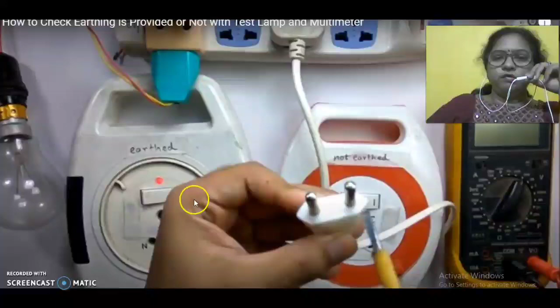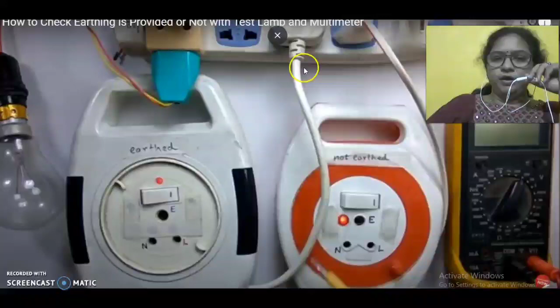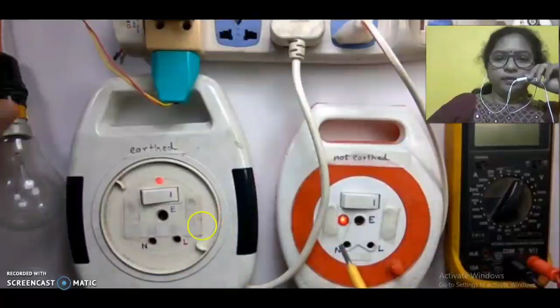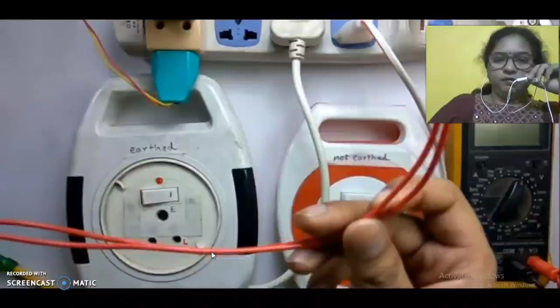Now how to check this earthing? This is a 2 pin socket where neutral and line terminal are there, and earthing is not provided, so this is not earthed, and this is the earthed one. The left side is the supply system which is earthed, where 3 pin is provided. Now whether earthing is there or not, you can check with the help of a test lamp. Here the test lamp means nothing but an incandescent bulb connected with 2 wires and a holder, and this test lamp will be useful for checking whether your supply is having proper earthing or not.